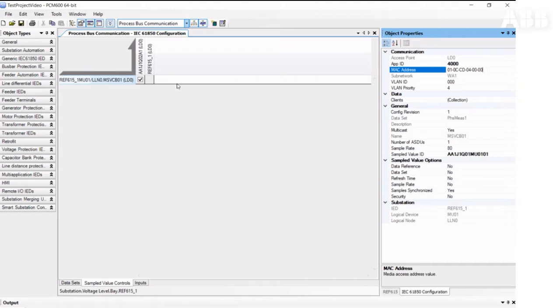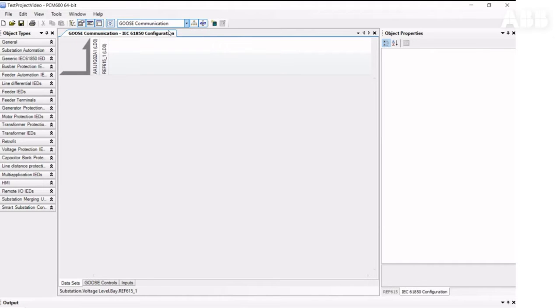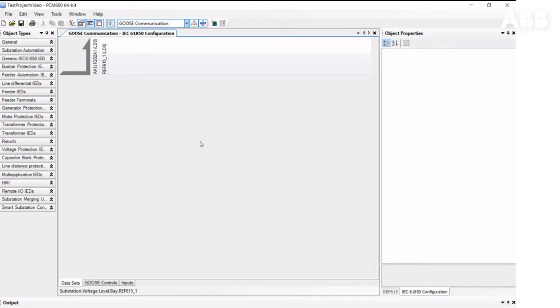The next task will be to put in place the GOOSE communication. In this application, we will use blocking-based current protection logic, where REF-615 is our outgoing feeder and REF-620 is our incoming feeder. If instantaneous overcurrent protection picks up on your outgoing feeder, it must block the instantaneous overcurrent protection of the incoming feeder.